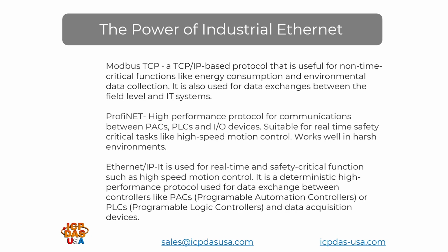PROFINET is a high performance protocol for communications between PACs, PLCs, and I/O devices. It's suitable for real-time and safety-critical tasks like high-speed motion control. This is because it uses TCP and UDP IP for communications that are not time-critical, but for time-critical communication it is able to bypass layers of communication, which gives it the necessary speed.